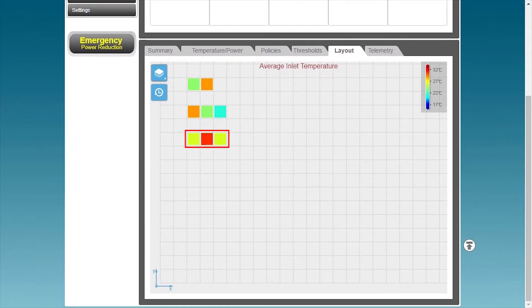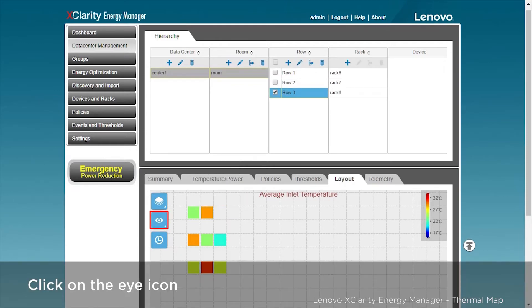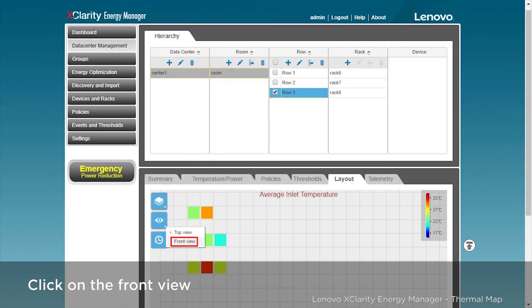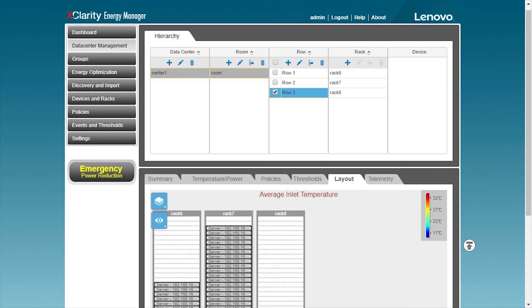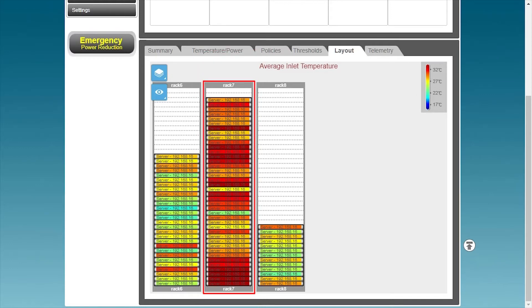Take the third row of racks as an example to see which servers in these racks have relatively higher temperature. First, locate row 3, then select the eye icon on the left in the physical layout to switch to the front view. In the front view, we can quickly and intuitively see that there are several servers in rack 7 with high temperature. As a result, the data center administrator is able to locate the server with higher temperature in the server room based on this view, and understand about the cooling condition of the data center.